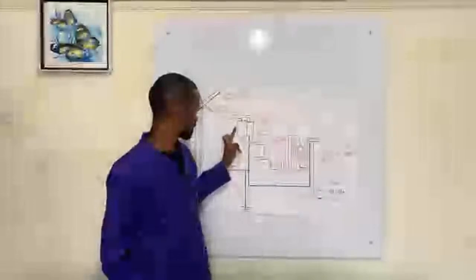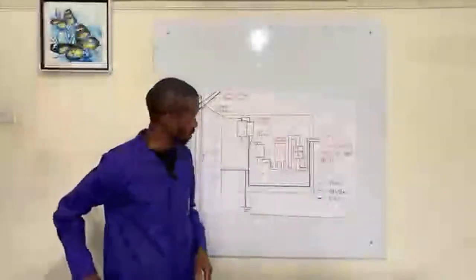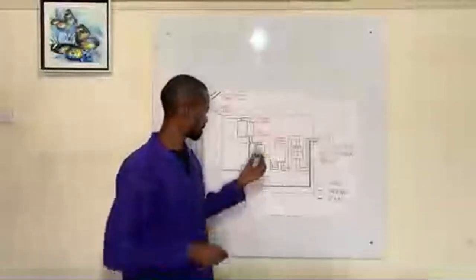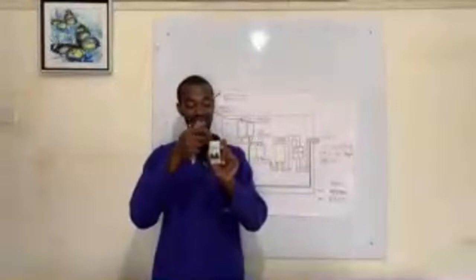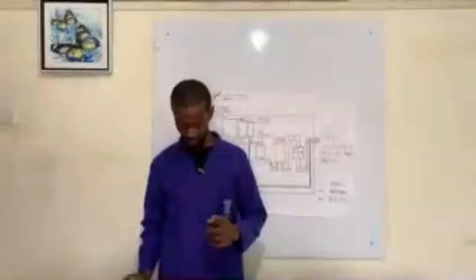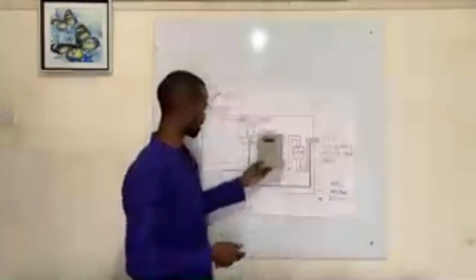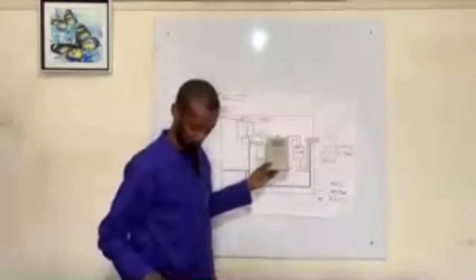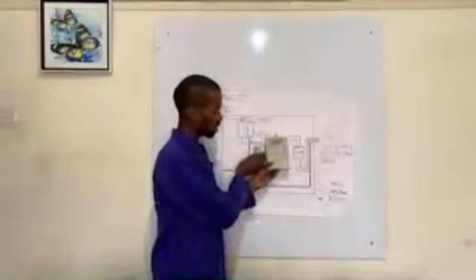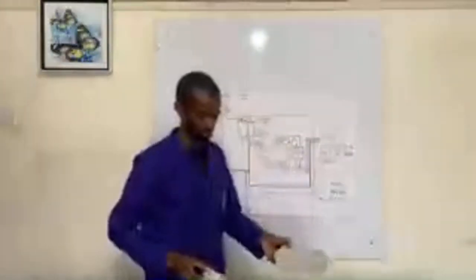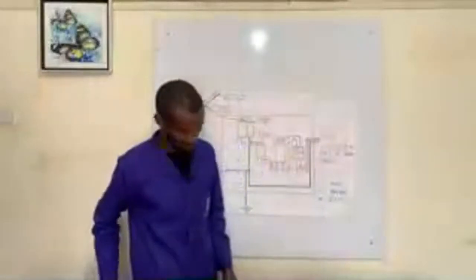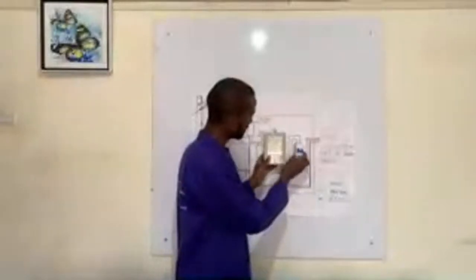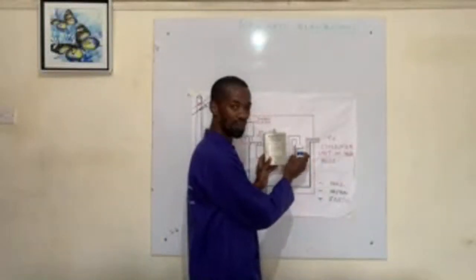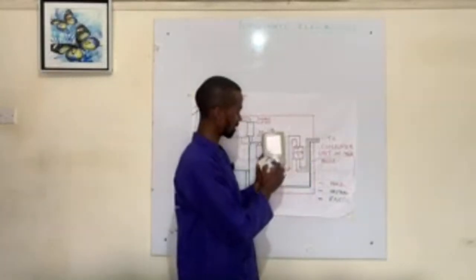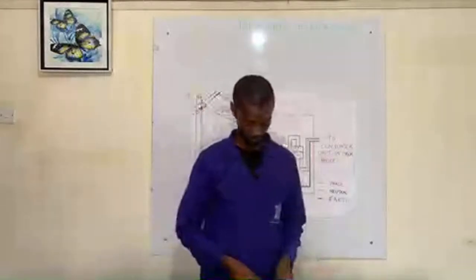Now, from this cutout that I've shown you, we will also have a double pole MCB. This is a double pole MCB, meaning it switches the live or the phase as well as the neutral. Then from there, like I have demonstrated, we have the energy meter. This double pole will switch power to this energy meter, which is just for demonstration purposes. From the energy meter, we will also have a second double pole switch. This switch purposely switches electricity from the energy meter all the way to the consumer unit.